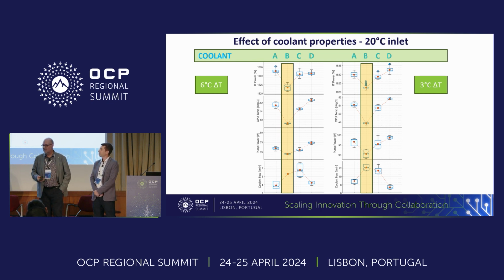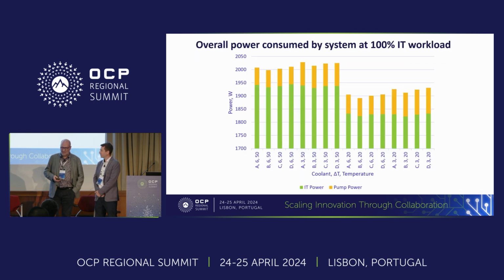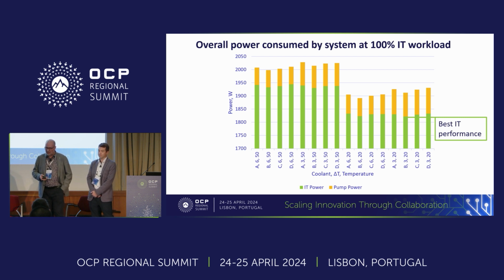The point I've made a couple of times about current leakages over the course of these 2 days. Probably everybody's fed up with me talking about that. So yeah, it's nearly a 5% difference in the total power draw between moving from 50 degree inlet temperature to 20 degree inlet temperature. That's significant, 5%. Yeah, so what you see here is the performance of the IT in the different cases. This is at 3 degree delta T and at 20 degrees centigrade. So you've got the lowest power draw for the same amount of workload. We're doing the same amount of IT workload.